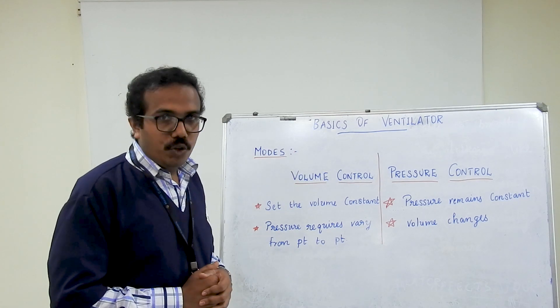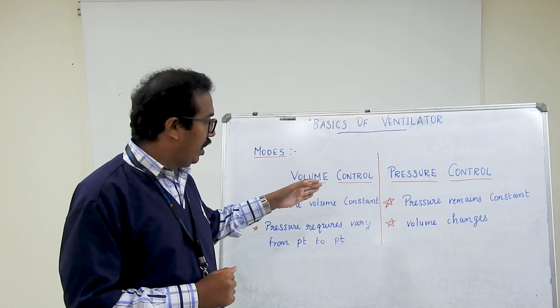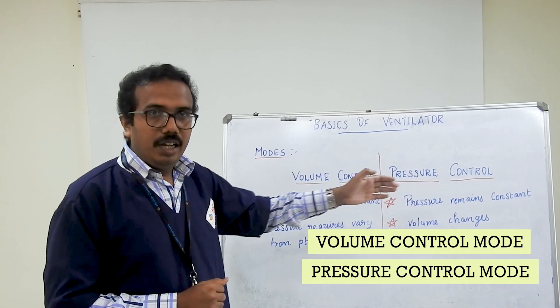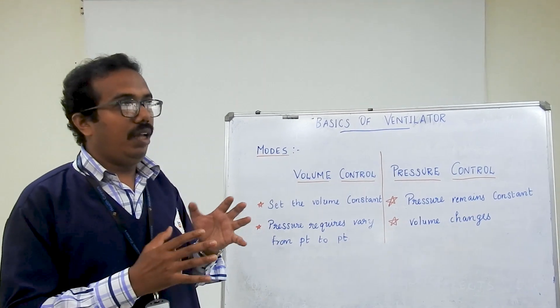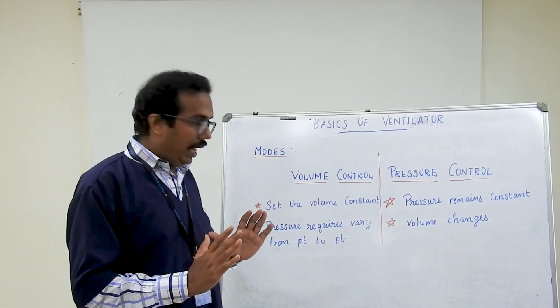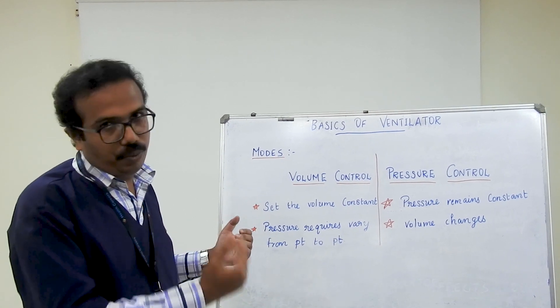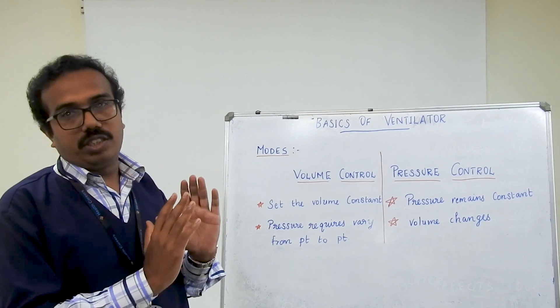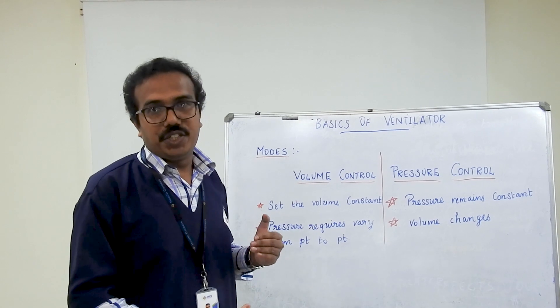Next, we will see the modes of ventilation. The electronic function is divided into two modes: one is volume control mode and another is pressure control mode. In volume control mode, we set the volume of air to push in per minute, so the volume remains constant while the pressure required may vary from patient to patient. In pressure control mode, the pressure of the air remains constant and the volume required may change from patient to patient.